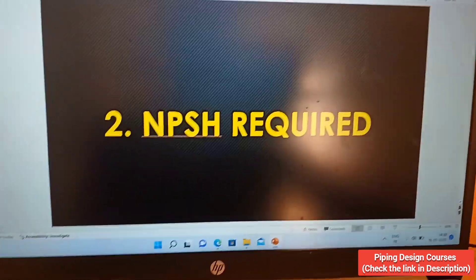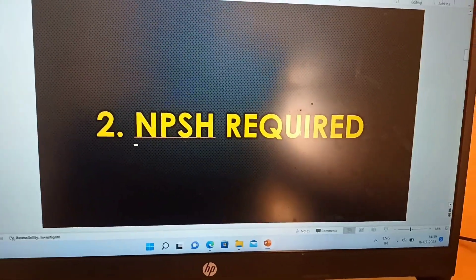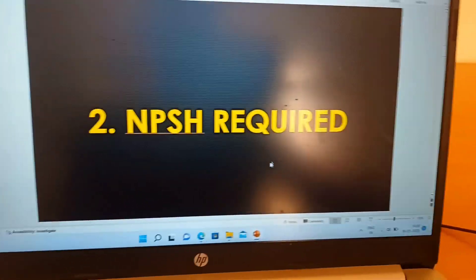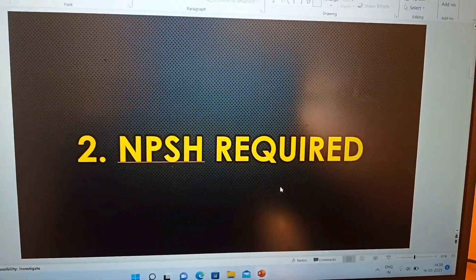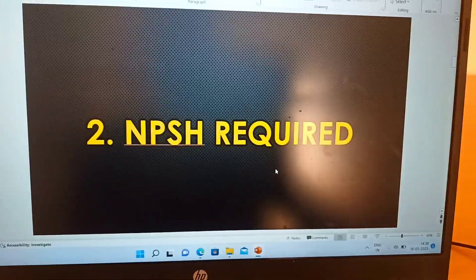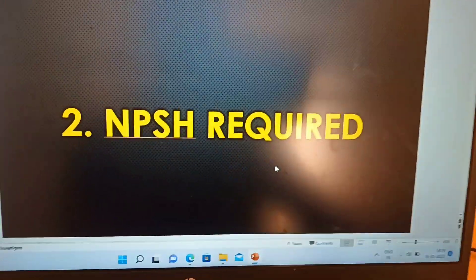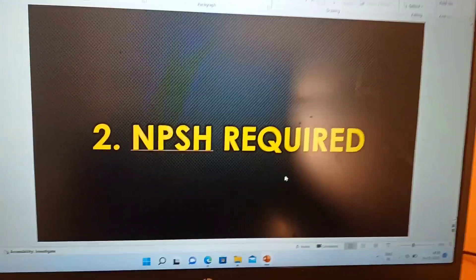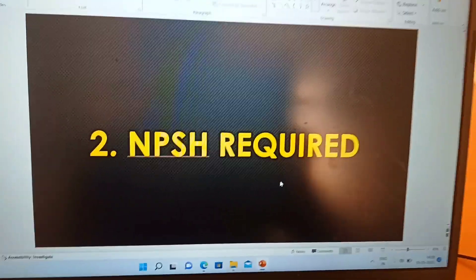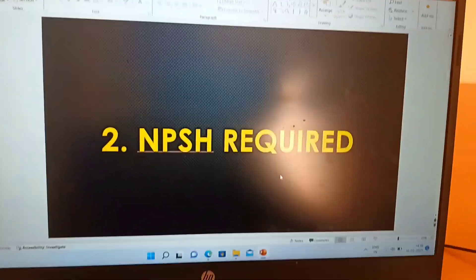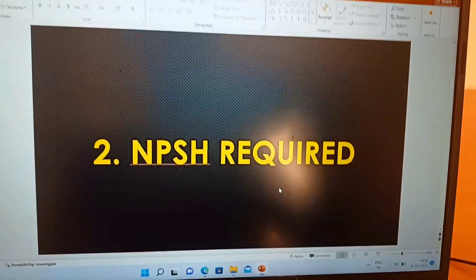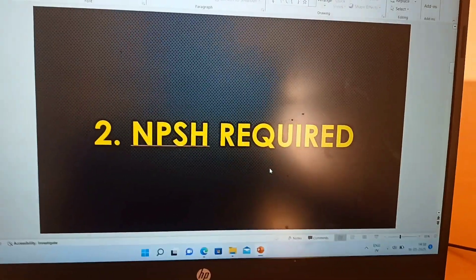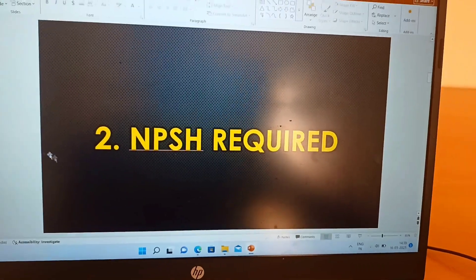The second point is NPSH Required — Net Positive Suction Head Required. Generally, in a process data sheet, the NPSH Available will be given, and the vendor will provide the pump to meet that requirement. In some cases, the NPSH Required may be higher than the NPSH Available due to process conditions, and in that case you might have to change the elevation of the pump. That is one key reason why NPSH Required is important information to verify in the vendor offer.